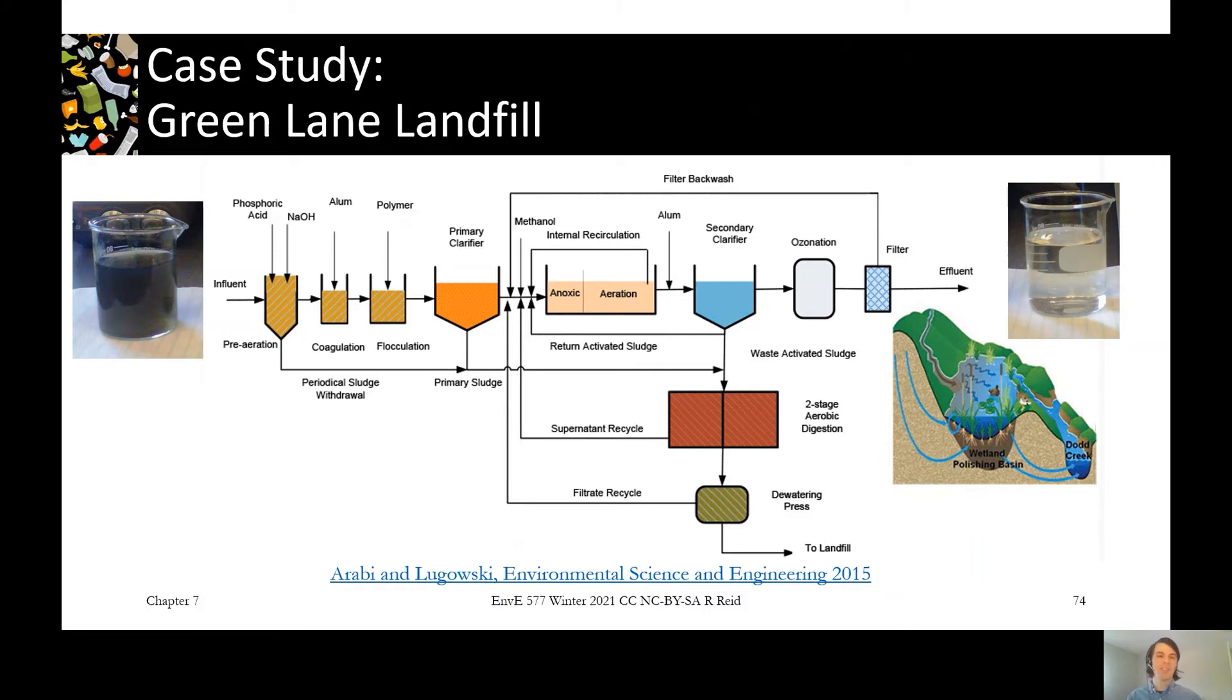So we want to make sure that while it's sitting in our leachate treatment facility, it's not continuing to produce methane and things like that. So there's a pre-aeration to start aerating it. You can see they're dosing phosphoric acid and that's to adjust that nitrogen to phosphorus ratio to make sure our microbes are going to be happy later on.